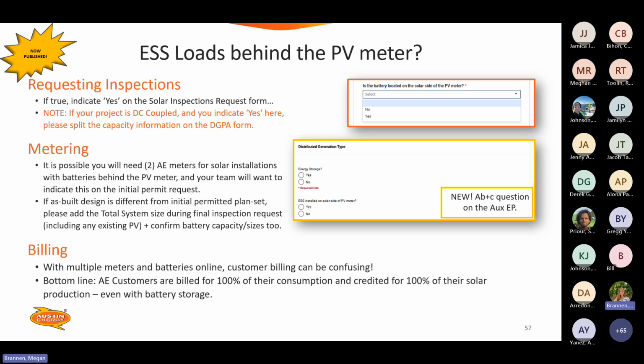If, however, it is a completely drastic change, or if your system size went from like 10 kW to 50 somehow, I've never seen that, but if for some reason that happens, we'll ask you to make a modification to the permit. But just keep in mind those are things we can do at or before that inspection. All right, with multiple building meters and batteries online, customers' billing can be confusing, so just keep in mind when you're talking to folks, AE customers are billed for 100% of their consumption, everything they consume on site, regardless of the source, and then credited for 100% of their solar production, even with battery storage.